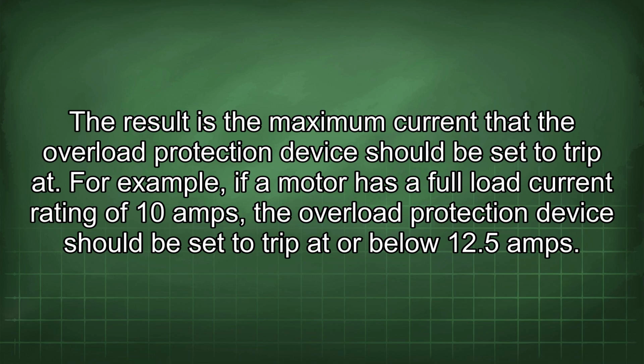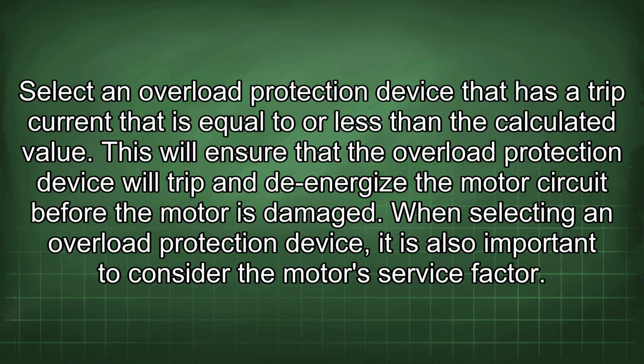For example, if a motor has a full load current rating of 10 amps, the overload protection device should be set to trip at or below 12.5 amps. Select an overload protection device that has a trip current that is equal to or less than the calculated value. This will ensure that the overload protection device will trip and de-energize the motor circuit before the motor is damaged.